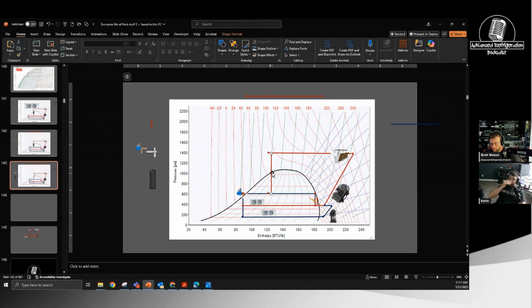Like at times it's running 97 degrees, you could see the level, it was like 80% level and had a little bit of flow, so it's going towards the HPV. It had flow, like it was 80% liquid and you could see the vapor at the top before. See, that's what I mean. So I don't know if the flow slowed down a little bit, and then that's where you get that mixture, basically that lava lamp. But it was like that for like 20 minutes.